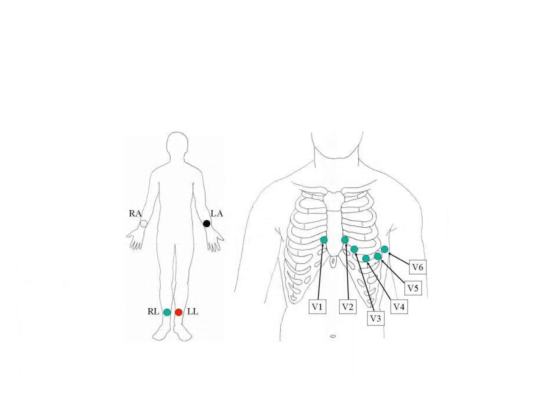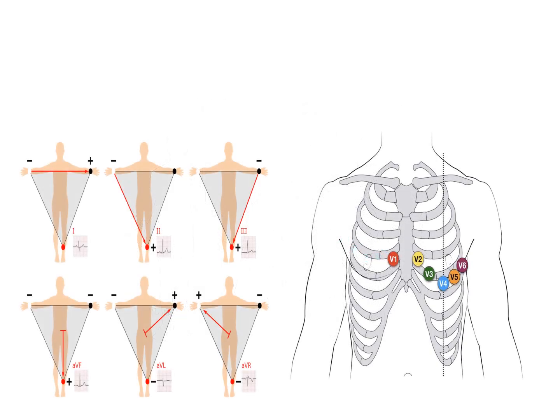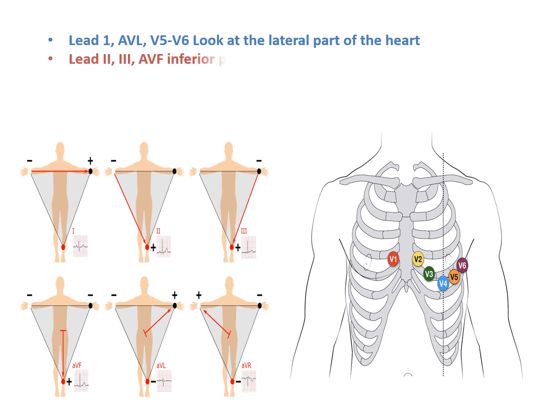The normal 12-lead ECG is recorded using 4 limb electrodes and 6 chest electrodes, and each lead gives a slightly different view of the heart. Leads I and aVL, V5 and V6 look at the lateral part of the heart. Leads II, III, and aVF show the inferior part of the heart. Leads V1 to V4 give a septal and anterior view.